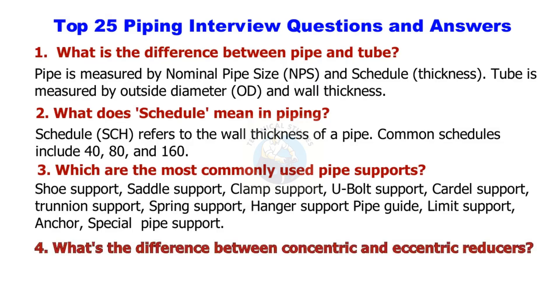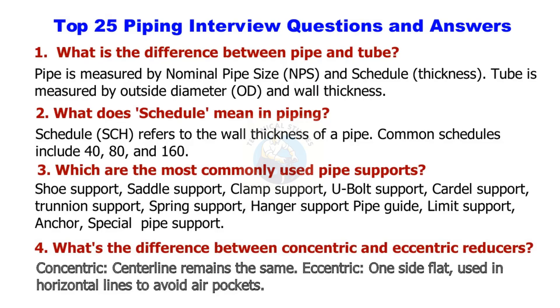What's the difference between concentric and eccentric reducers? Concentric: the centerline remains the same. Eccentric: one side is flat, used in horizontal lines to avoid air pockets.